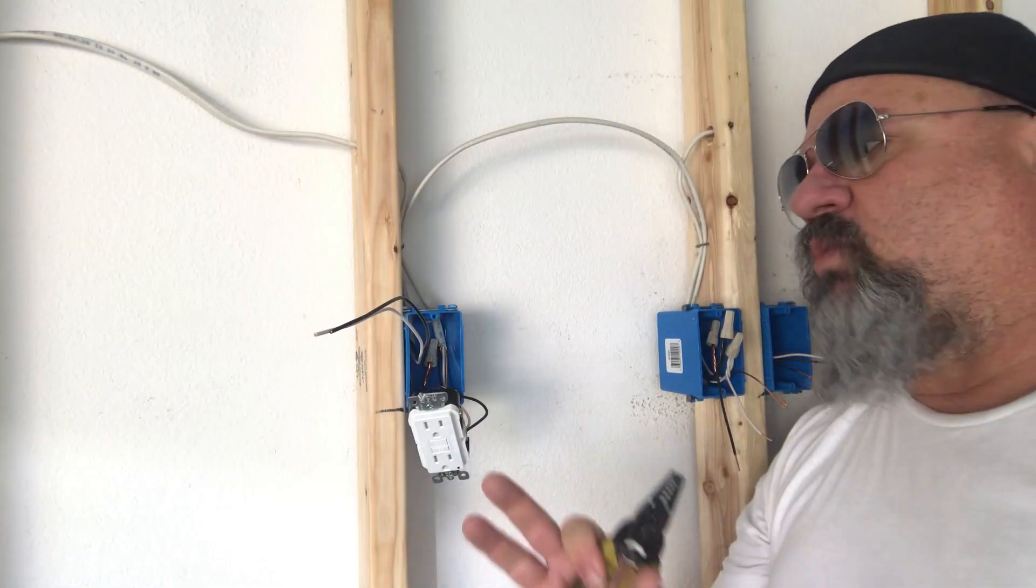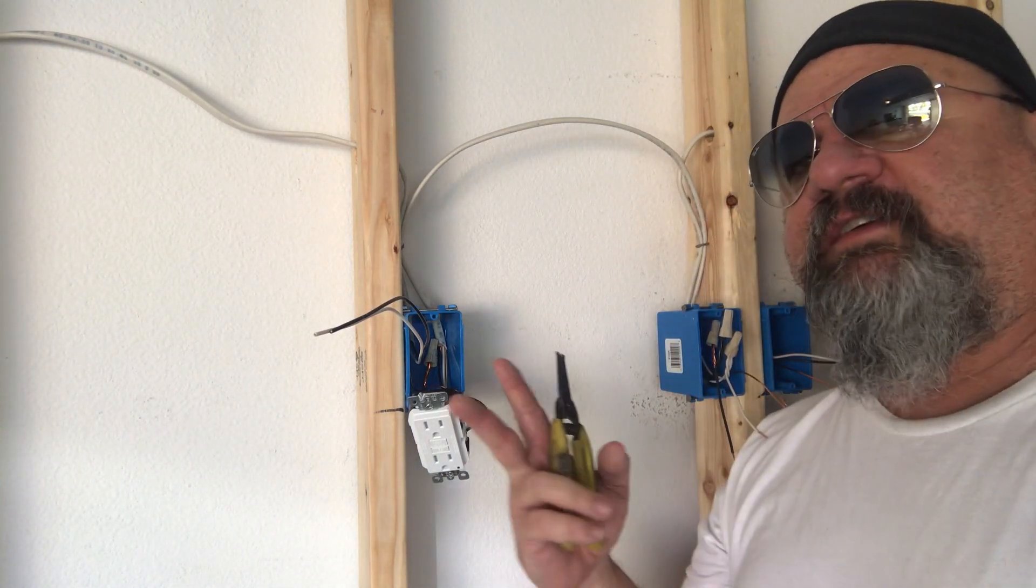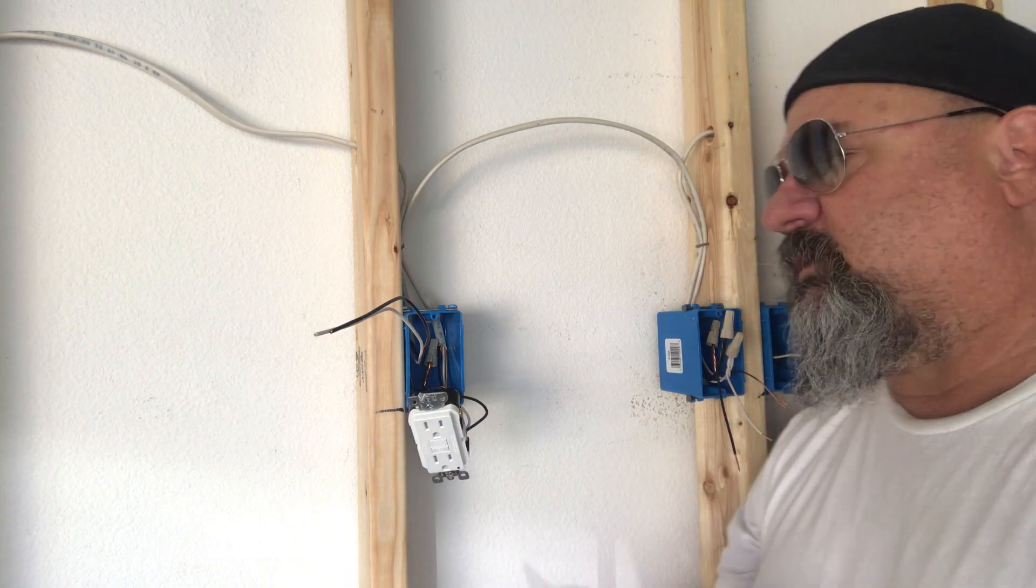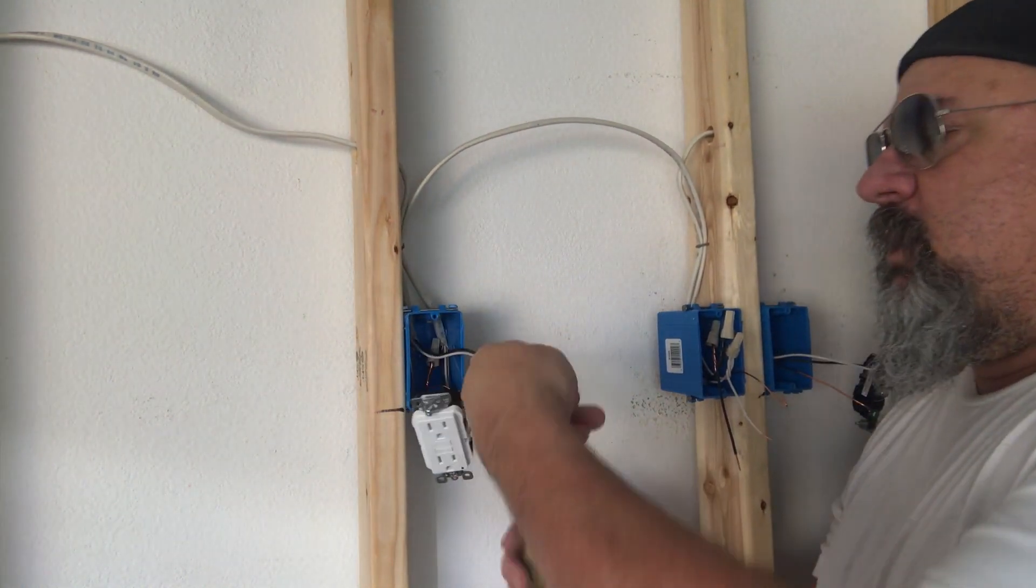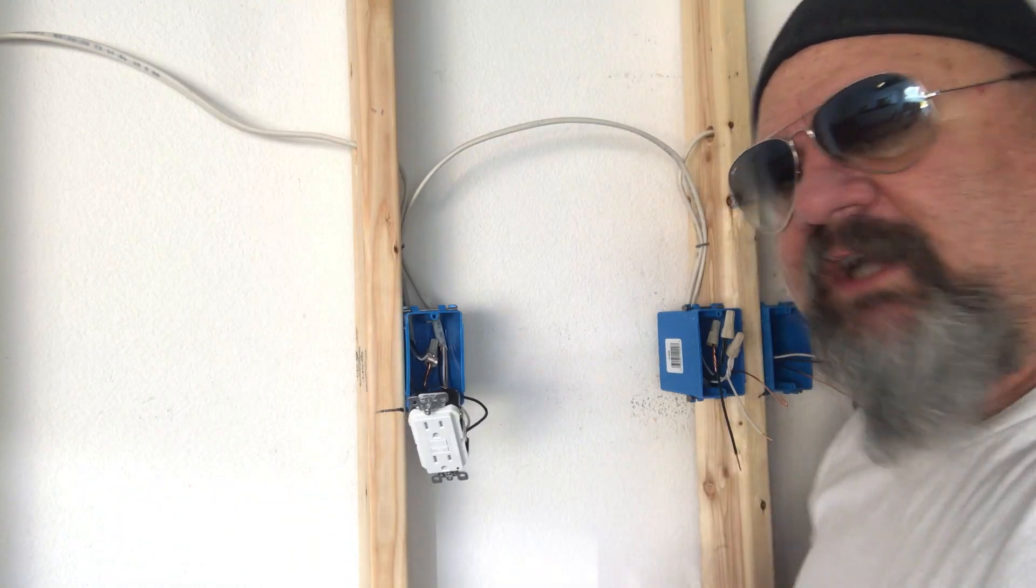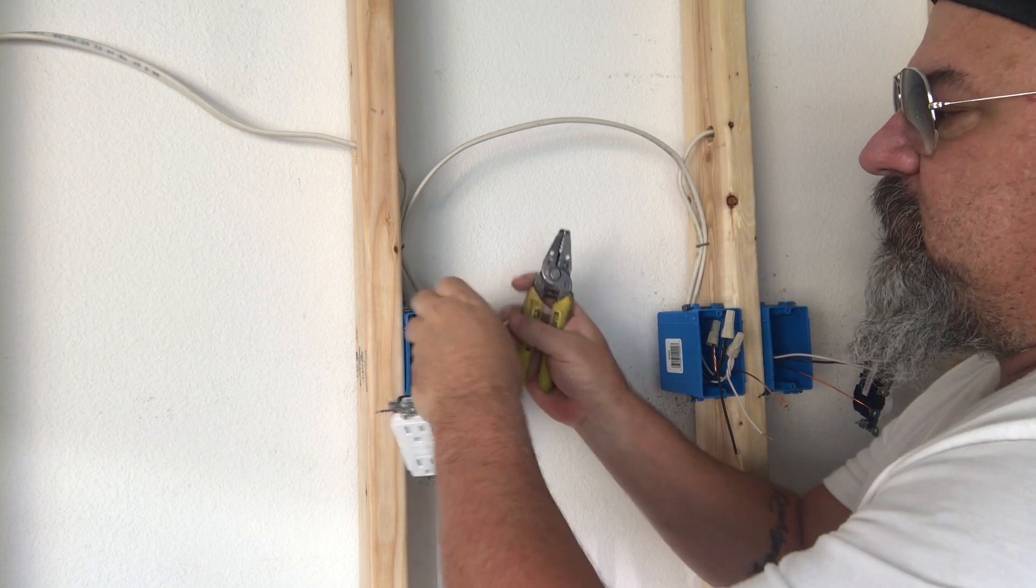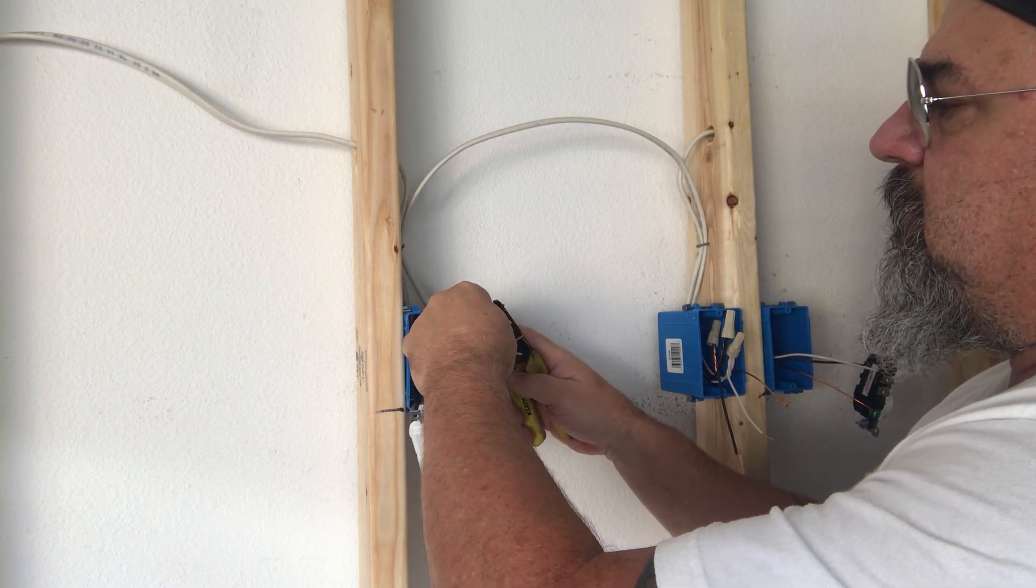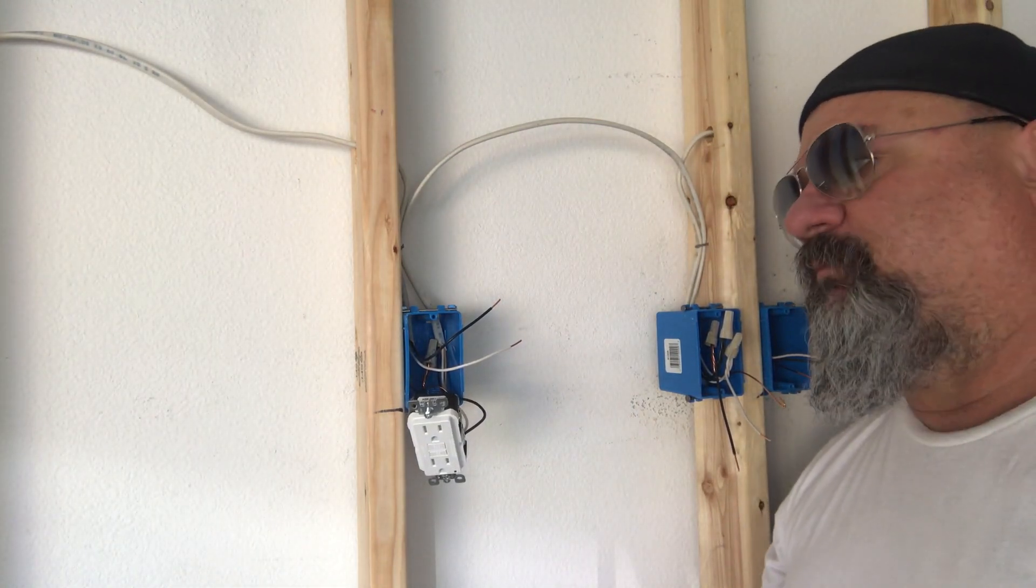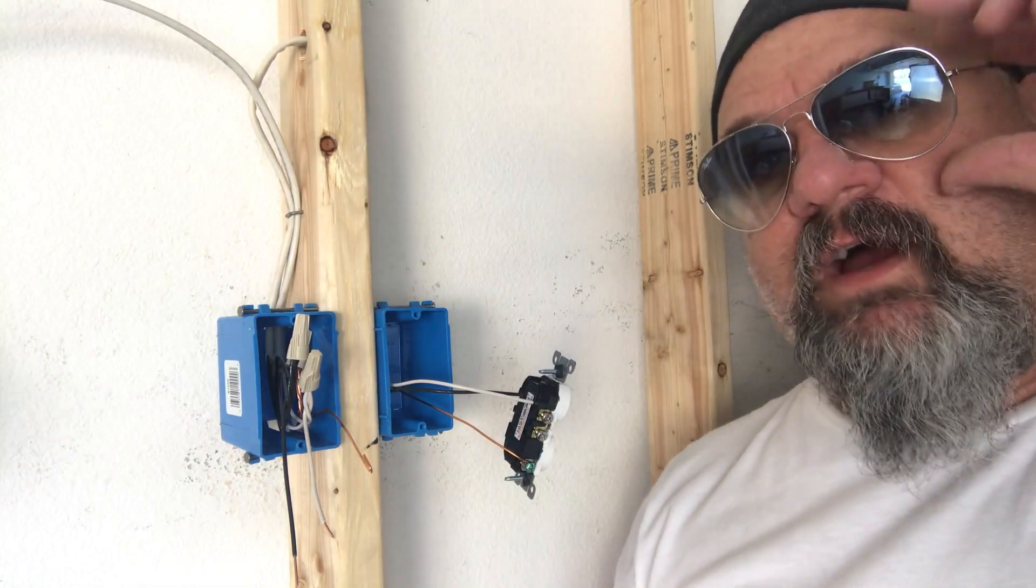And there we have the load side of it. Now we're going to install the line side, very simple. The reason why I do the load first is because if I would have stripped out all these at the same time, I might have got mixed up and forgot what I was doing, got distracted like a taco truck come by or somebody had a beer. I already have that hooked up. Now I have no doubt I know that this is my line side because the only two wires left in there, because I made it that way. So I'm just going to do just the way we did on the load side. The silver terminal for the neutral and then the gold terminal for the hot.